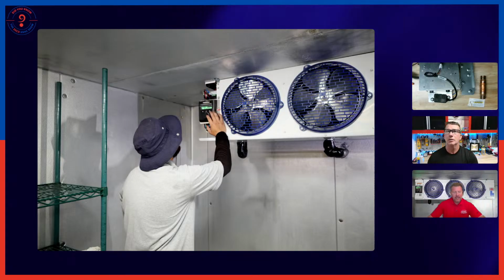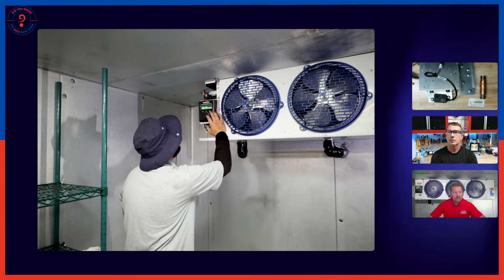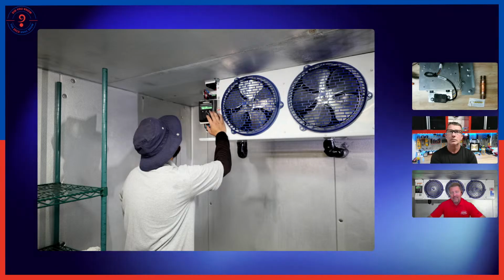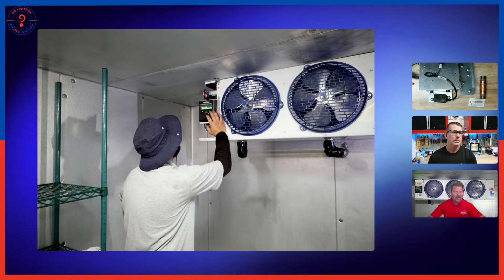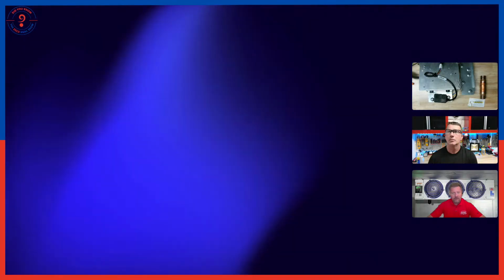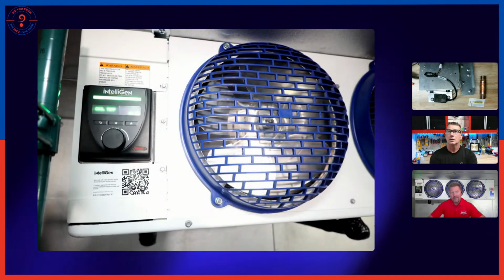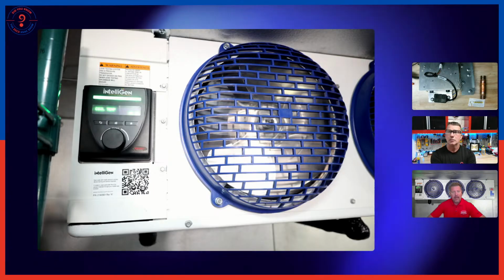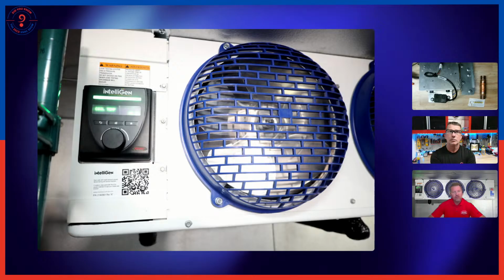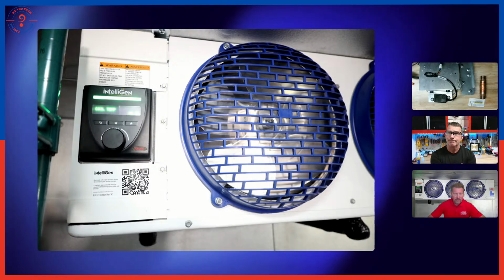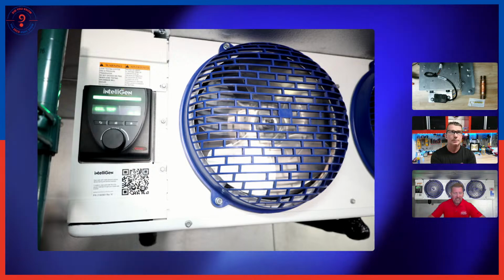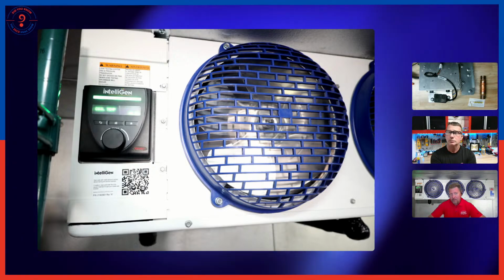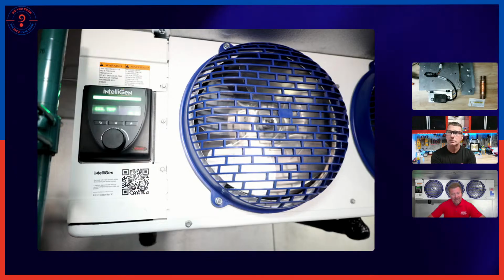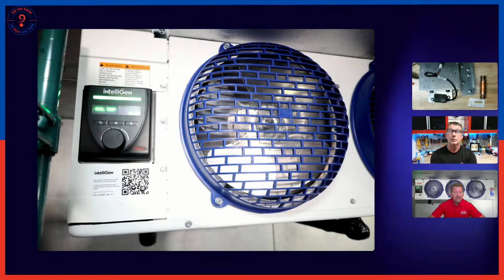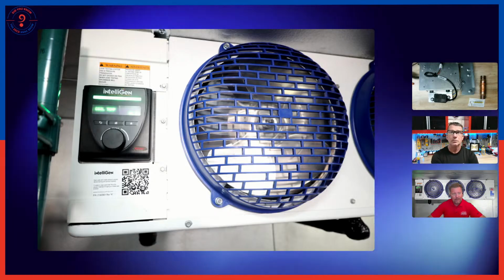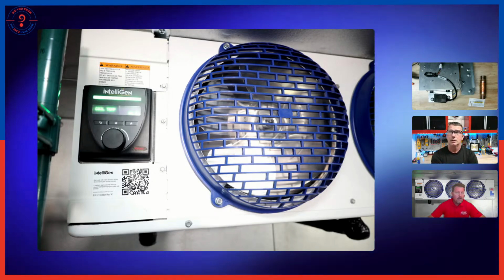So Intelligen is our latest electronic control system. Very basic, in my opinion. We're using an electronic expansion valve. Its primary purpose, again, is for temperature control. Once we call for cooling, it is controlling superheat. It's monitoring our suction pressure and suction temperature and adjusting that EEV to maintain 8 degrees of superheat, which is our factory default. And that is adjustable from 4 to 20. So we do have a range there. Some applications require lower, some require higher. So that is there.